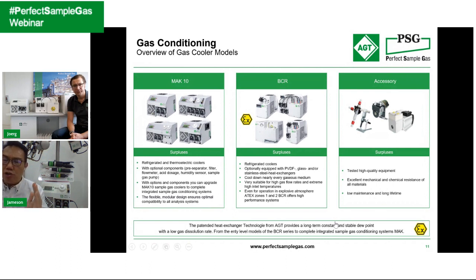This back pressure will change the dew point, and that will cause condensation. So how you regulate the flow meter is so important. This is particularly for the commissioning engineer. These are the 2 points, please take note. Let's go back to the gas cooler, which is the heart of the sampling system. Okay, maybe you can show one example, Jemson.